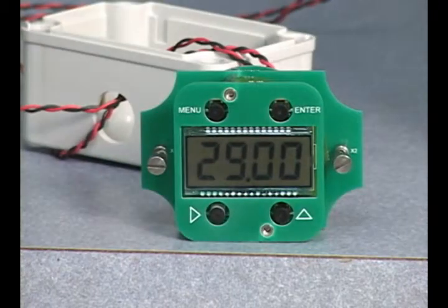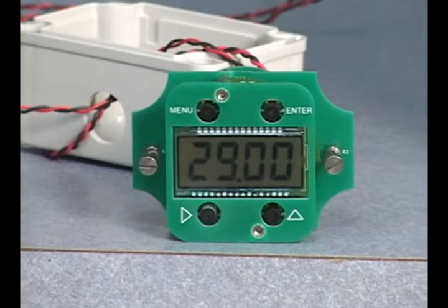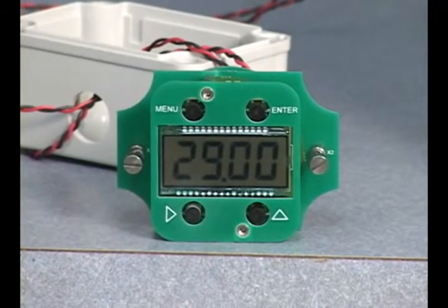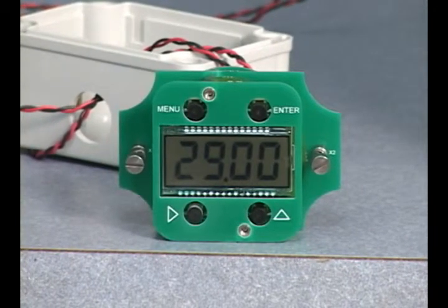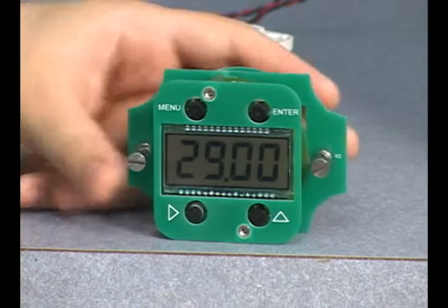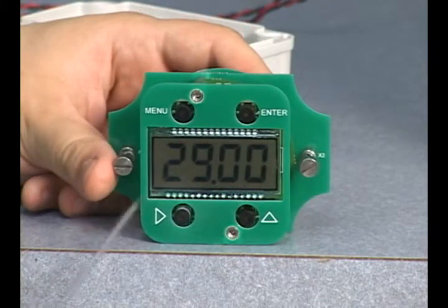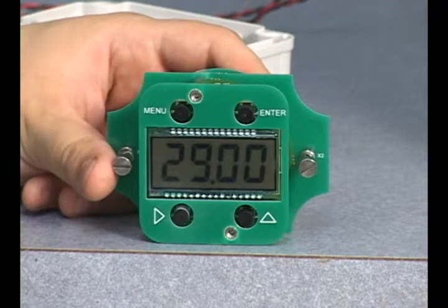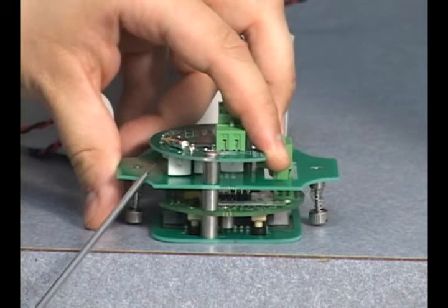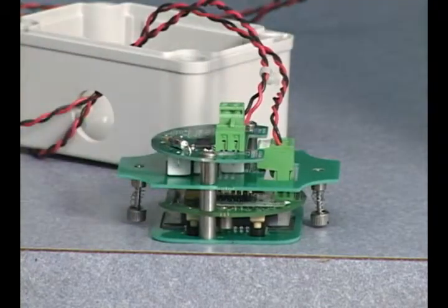This is superior to an enclosure heater, which needs to be sized specifically for the enclosure and has very strict power requirements. In addition, because the heater board is actually controlled by the microcontroller responsible for controlling the display, it means that these heating elements will only turn on when required due to the ambient temperature.